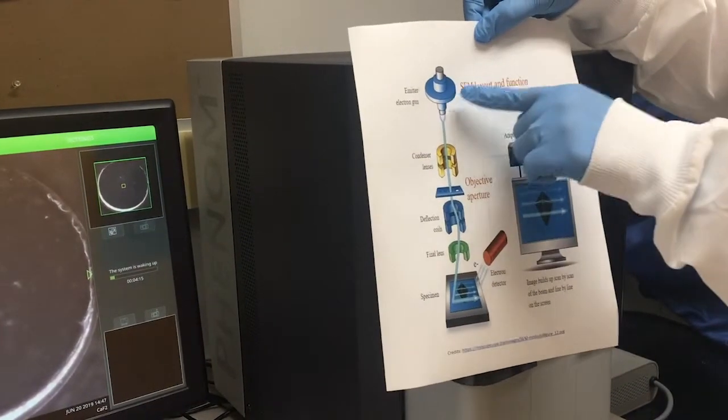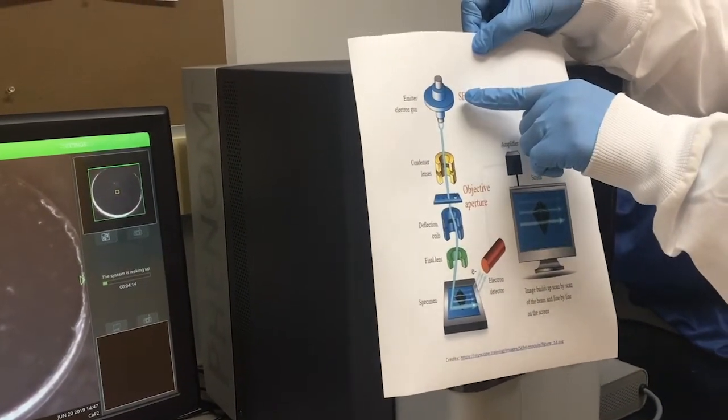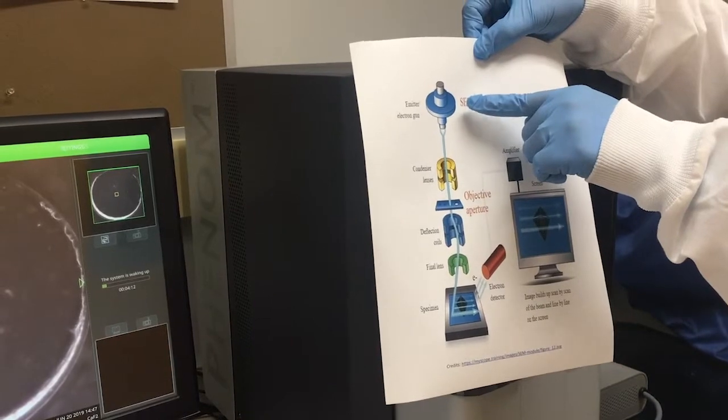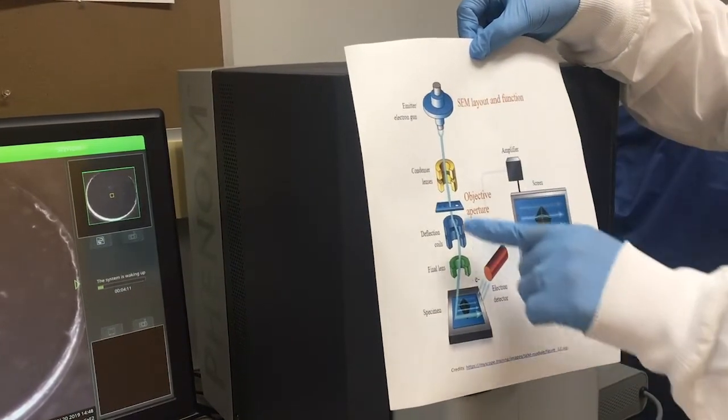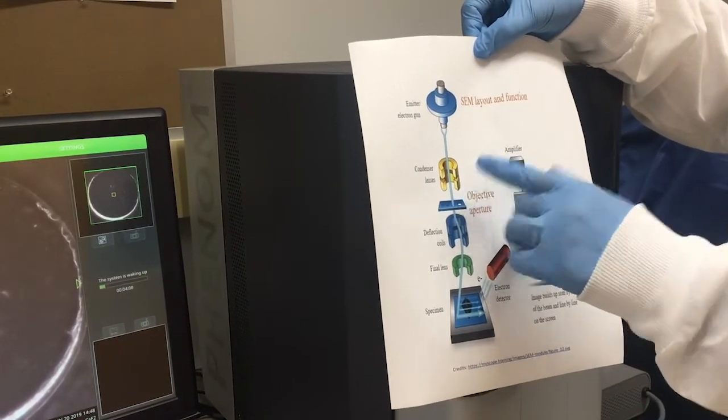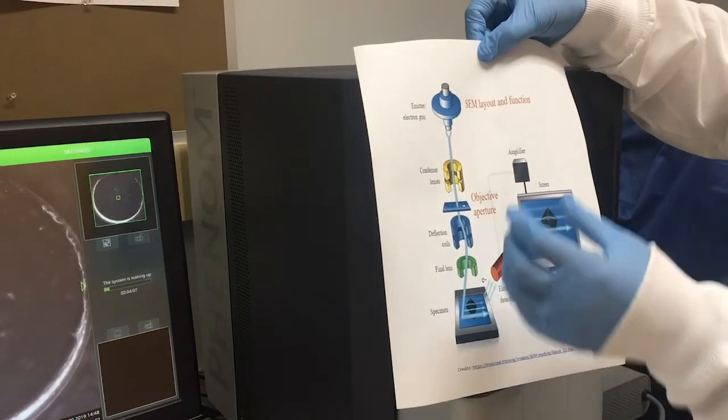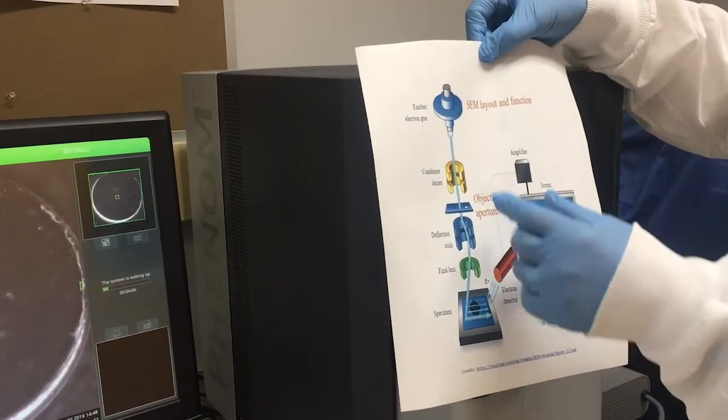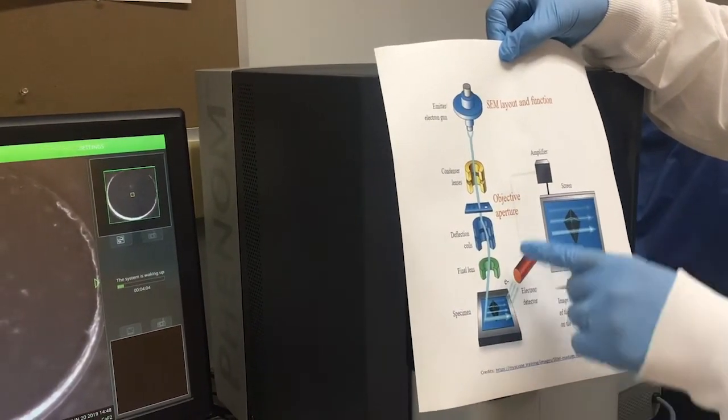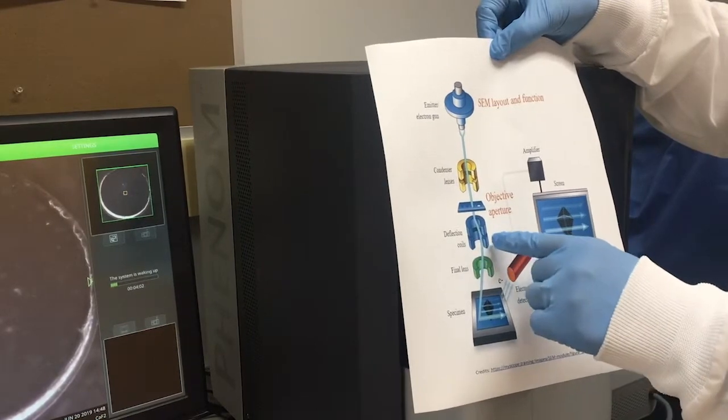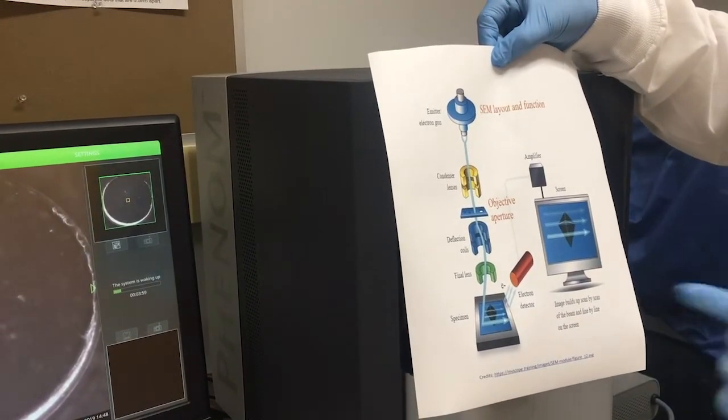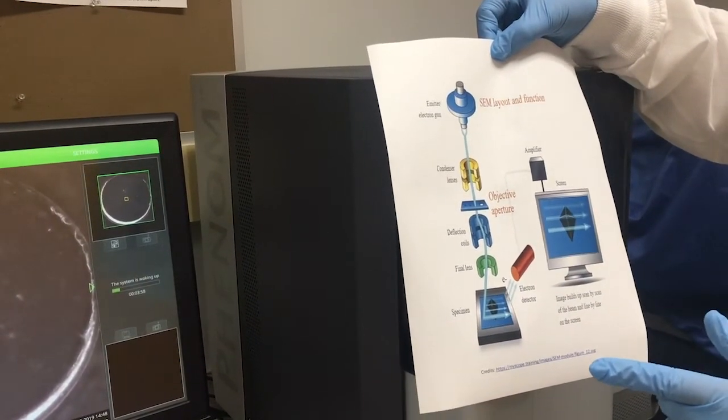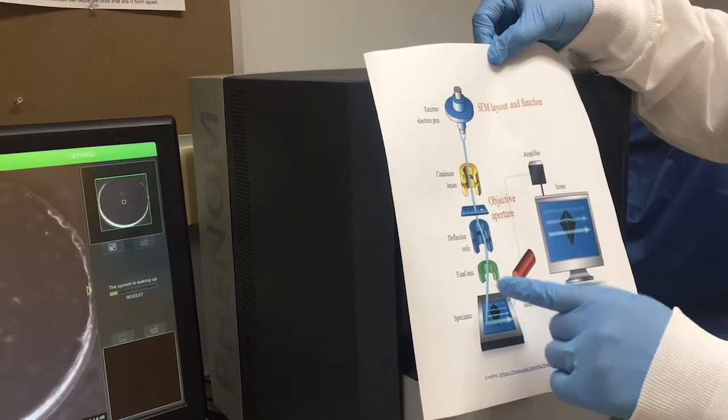This is the electron gun, which is the source of high-energy electron beam, and then there are a series of electromagnets which control the intensity and focus of the beam. The scanning coils scan the sample, and as the focused electron beam hits the sample, several signals are generated, which are collected by the detectors.